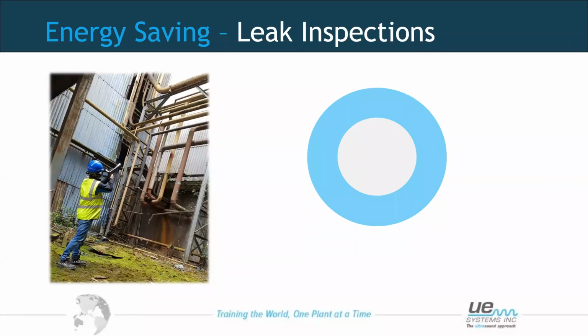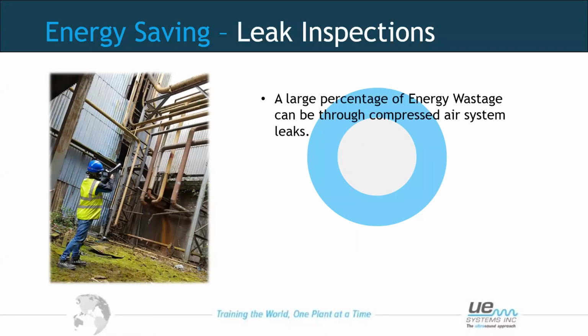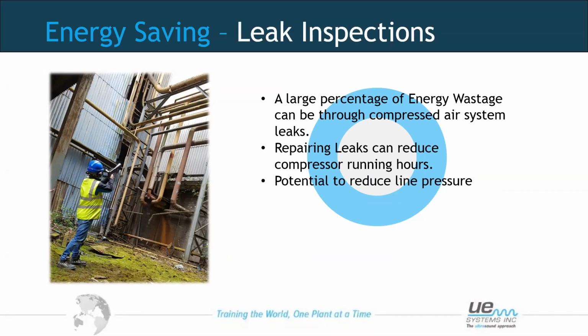So going on to energy savings with leak inspection, a large percentage of our energy wastage can be through compressed air systems. Repairing the leaks can vastly reduce our compressor running hours. That's one of the important things behind this. We also have the potential, if we have a lower level of leakage within our site, to be able to reduce the line pressure of our system, which in turn is going to have another effect on our energy audits as well.